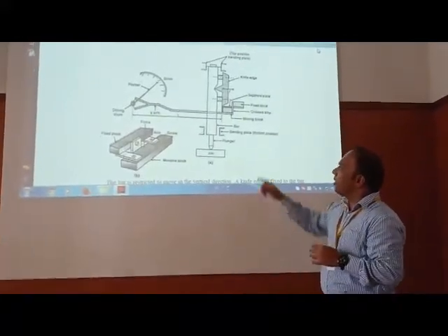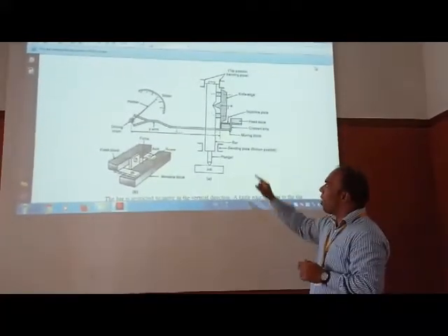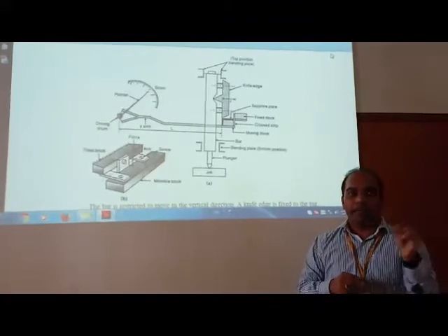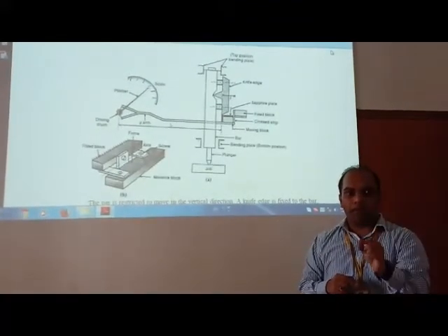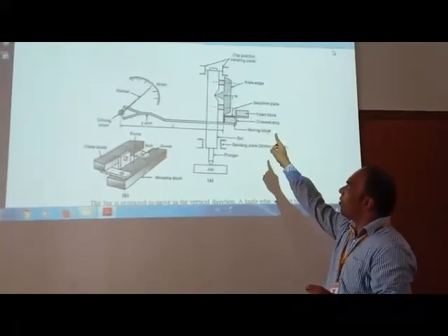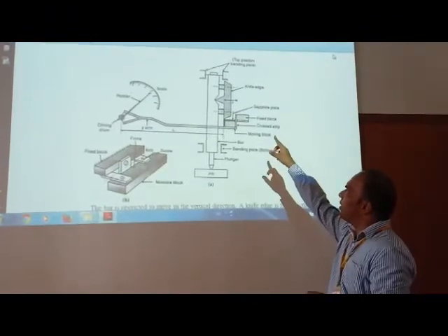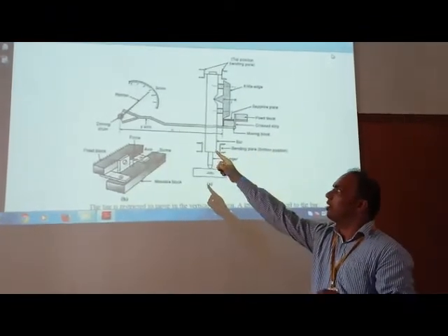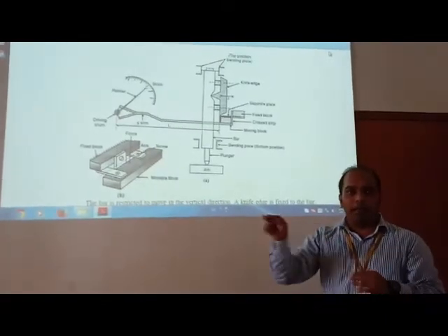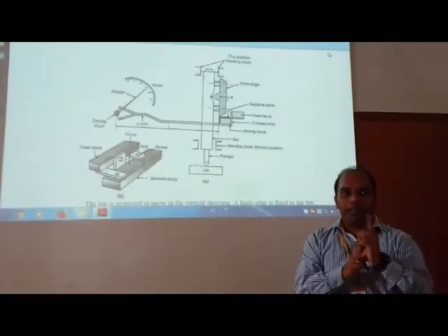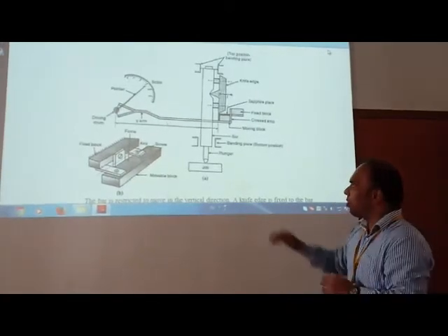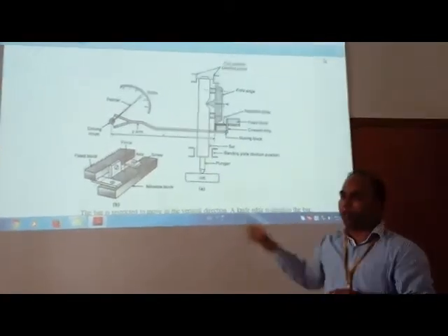Now, how the operation works: the job is placed at its position. The plunger will move up and down, that means in the Y direction. While moving, it will sense the crest and the bottom, and it will be a Y direction movement. That Y movement will be noted by the knife edge. The knife edge is connected to the cross strip that directly gives input to the driving drum. Dependent on the horizontal movement, the driving drum will give us the pointer movement, and that pointer movement is noted onto the scale. So this is the working of the sigma comparator.